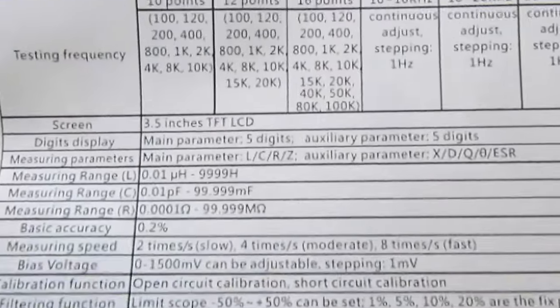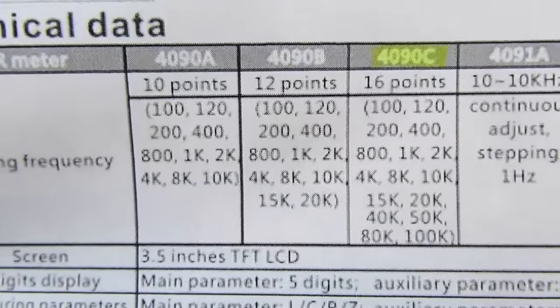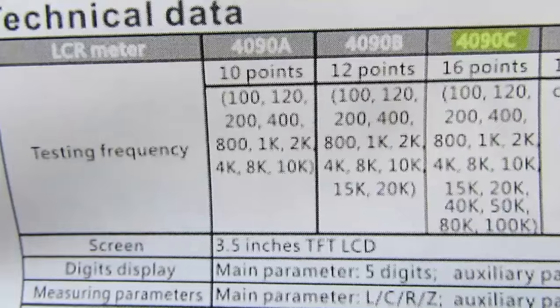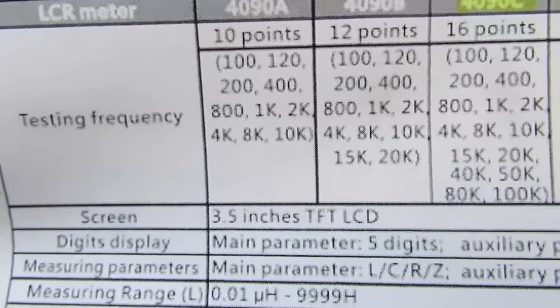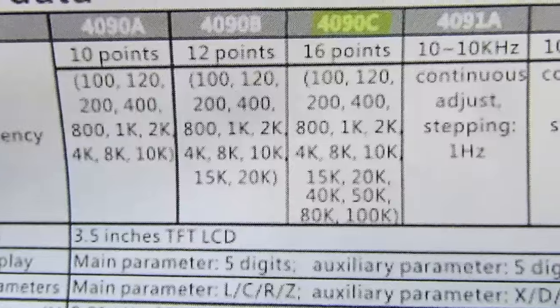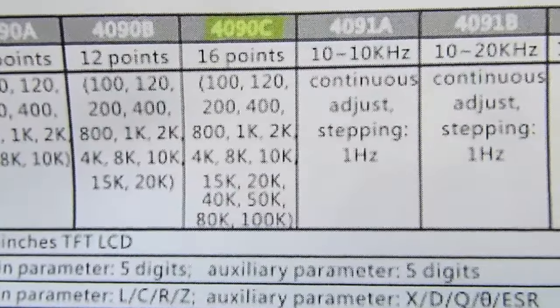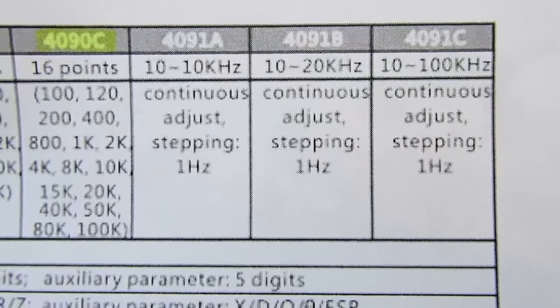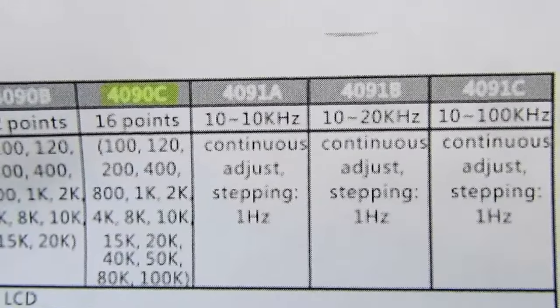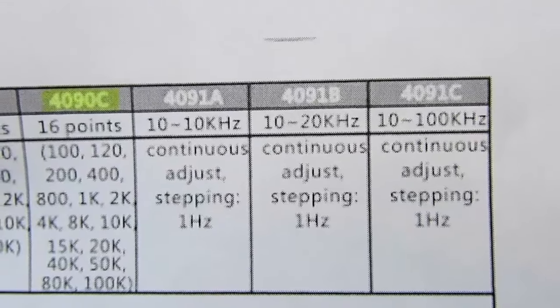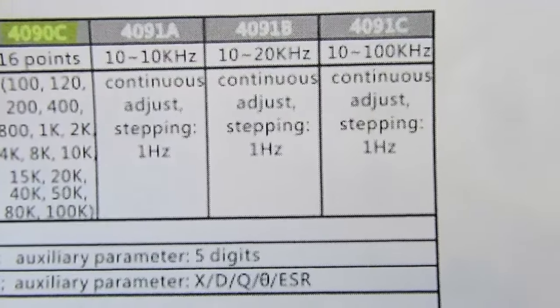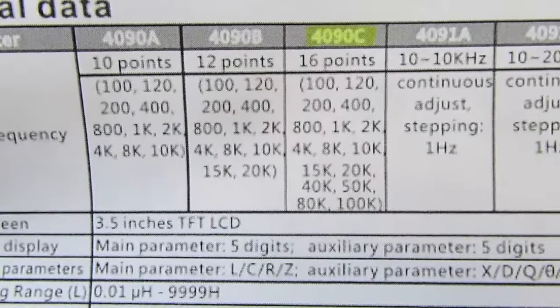The real distinguishing feature between them is how many frequencies you can test at. The cheapest model, the 4090A, has ten different frequencies between 100Hz and 10kHz. The 90B is 100 up through 20kHz, and the 90C is 100 up through 100kHz. The 91A, 91B, 91C have the same frequency range limitations, but instead of stepping through presets, they just have you enter the frequency you want.